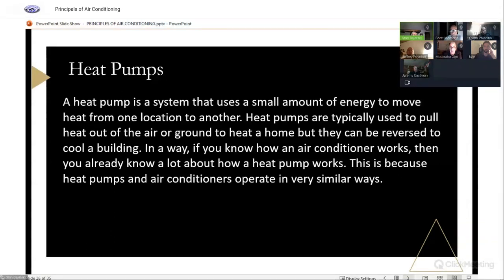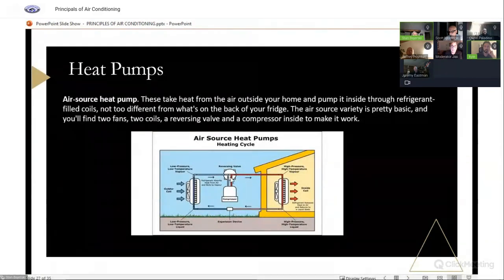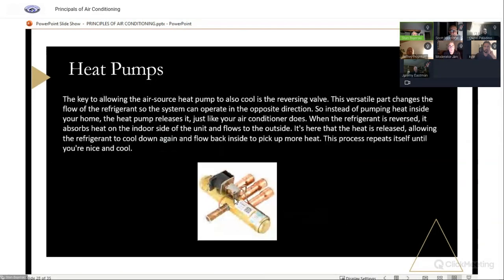When you're running that in the air conditioning mode, you're looking for the same things as you would on a central air conditioning system. Now we have mini splits with several coil sets on them. The only difference between a heat pump and a regular air conditioning system is the three-way valve, the reversing valve. And that looks like this, if you can see it in there. This is basically what it looks like with a relay on it. It changes the flow of refrigerant, so the system can operate in the opposite direction. So your condensing coil becomes your cooling coil, and your cooling coil becomes your condensing coil.